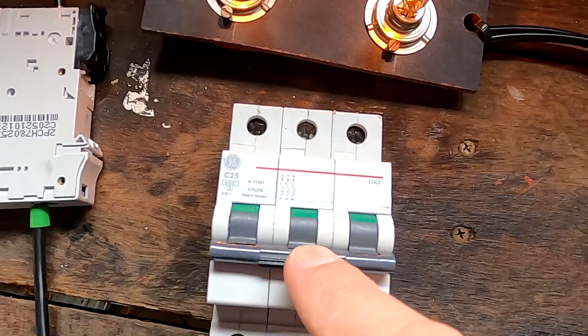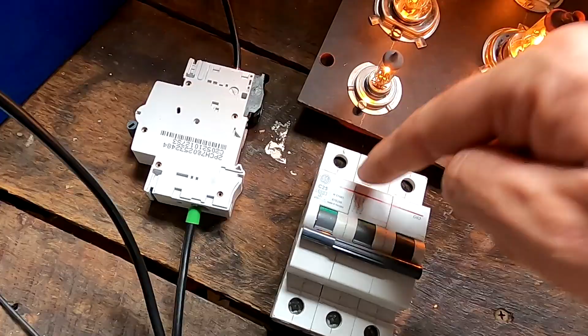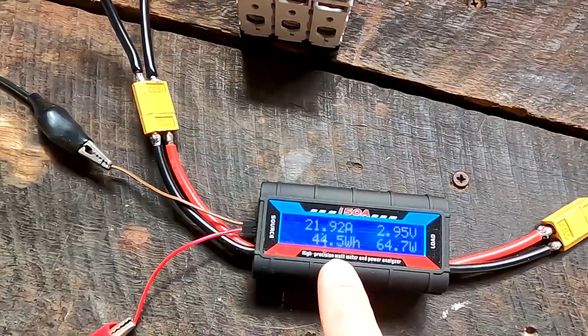I've got a 25 amp circuit breaker here, a 3-pole, but I'm only using one of these for that. So as soon as this one trips, I'll put this one in and continue the test. It doesn't really matter because this stays alive even without the battery connected, it has an external power supply.